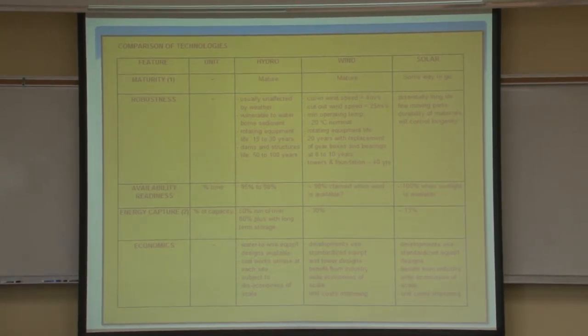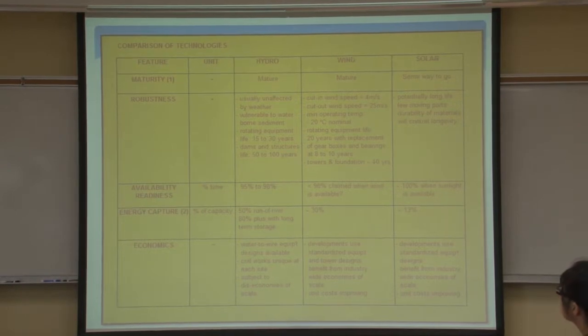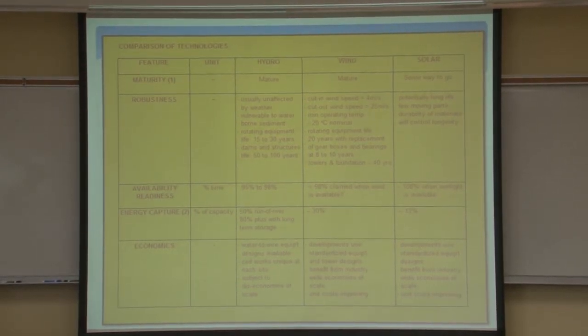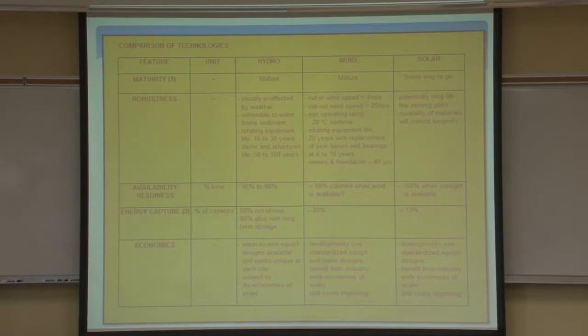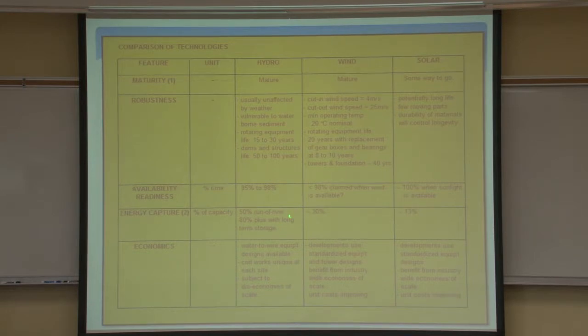Energy capture: this is the amount of energy that I can capture, within the capacity of the unit, because remember your energy input is variable. So in hydro, run-of-river, a typical amount is 50% of the flow energy available that can be utilized. With long-term storage, greater than 80% is quite a possibility. With wind, it seems to be in the order of 30%.